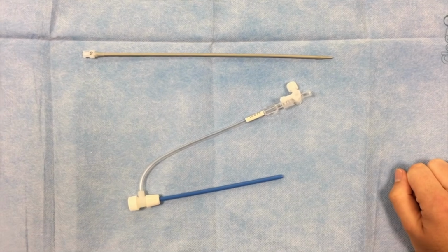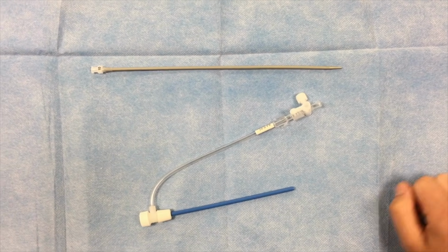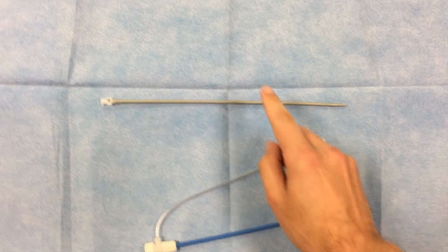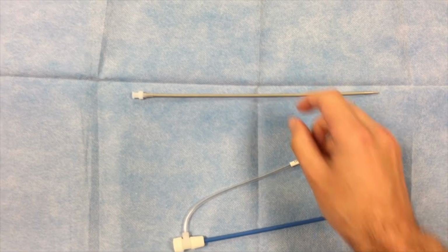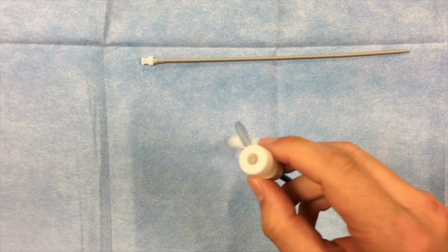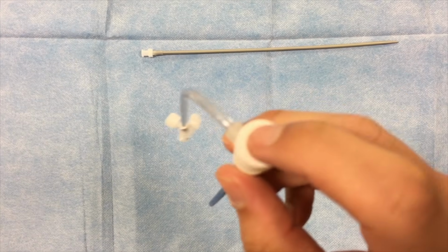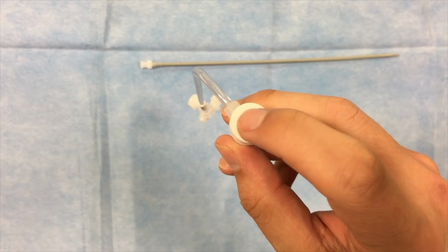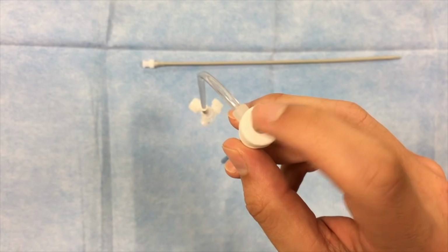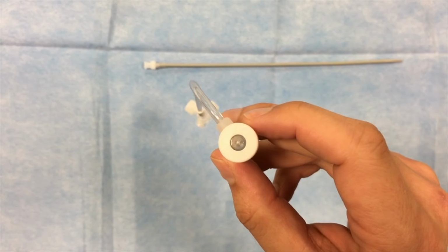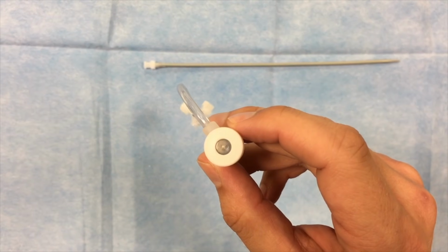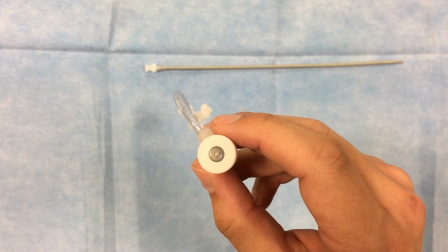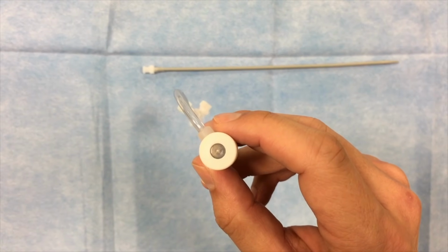So this is an example of a sheath on the bottom, and then the other object on top is a dilator, which is inserted through the sheath. If we pick up this sheath and look at this end, this is the end outside of the patient. And you can see it has a covering. So this is a one-way valve.